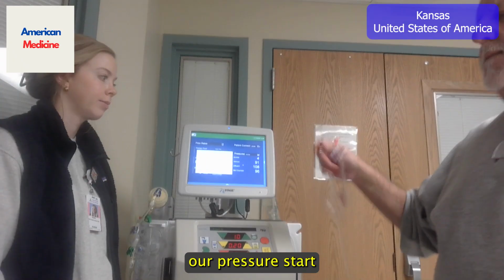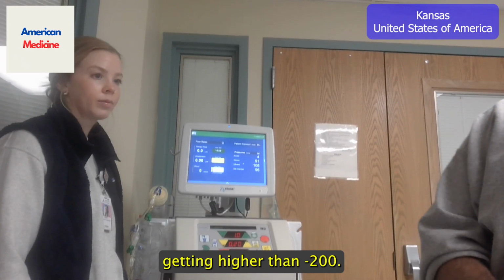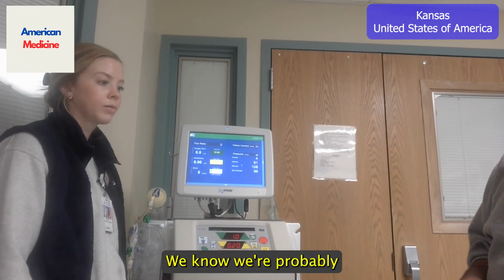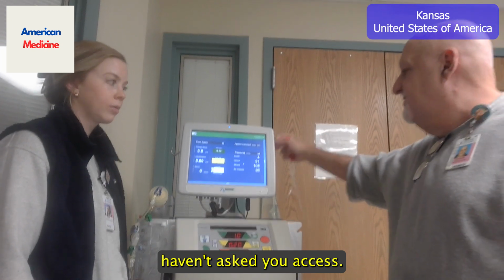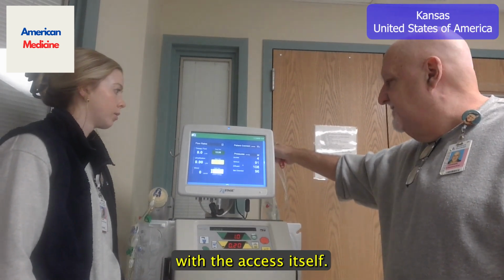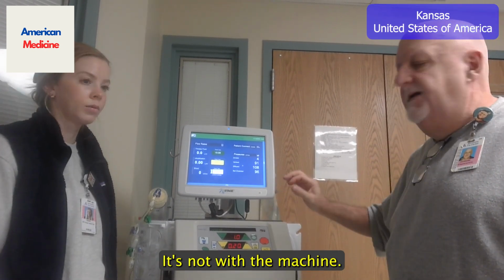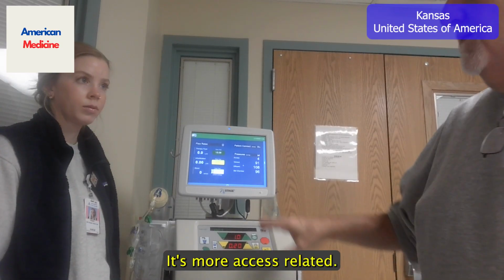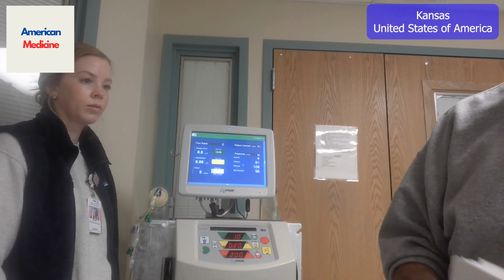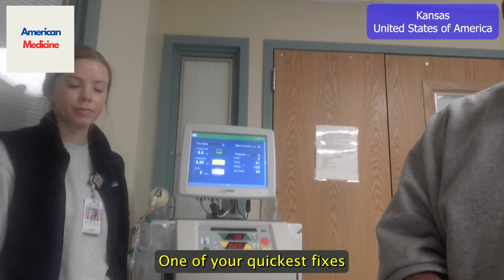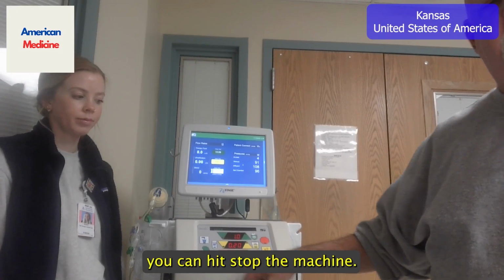and negative 200. Anytime our pressures start getting higher than negative 200, we know we're probably having issues with the access itself. It's not with the machine. It's not with it clotting. It's more access related. One of your quickest fixes is you can hit stop on the machine.